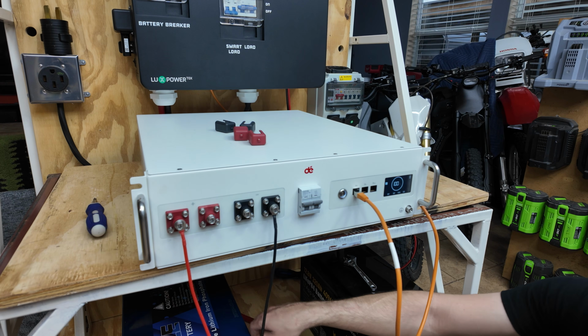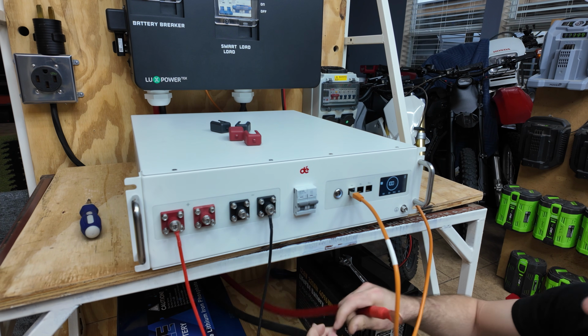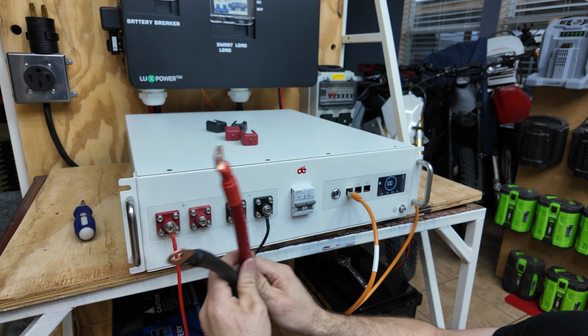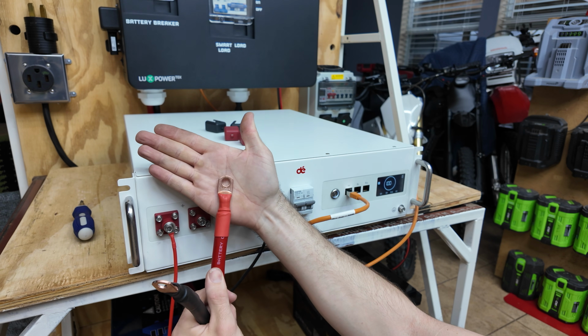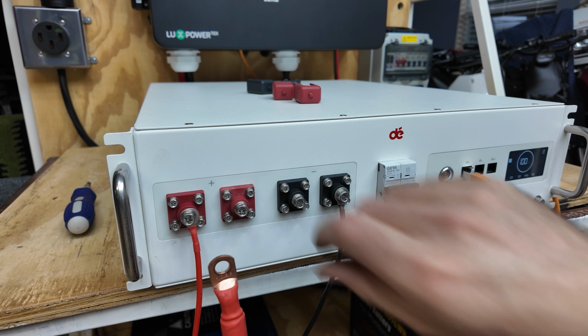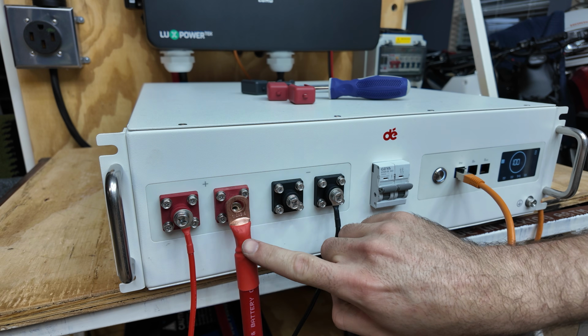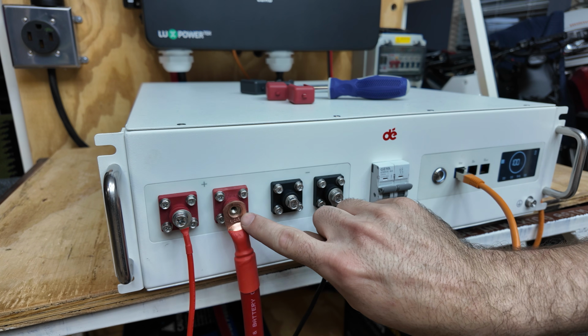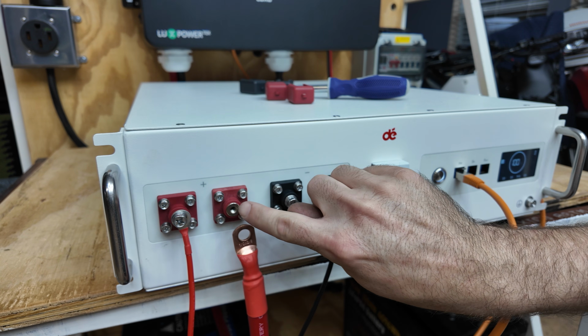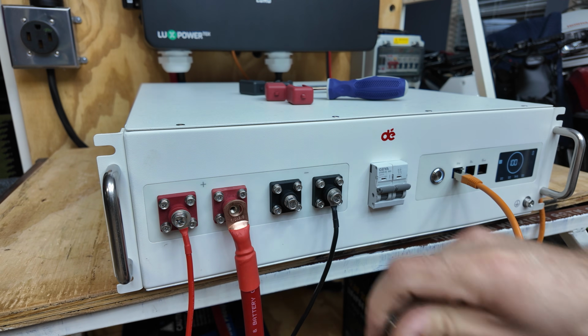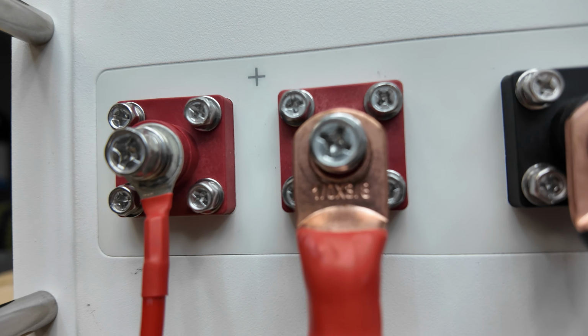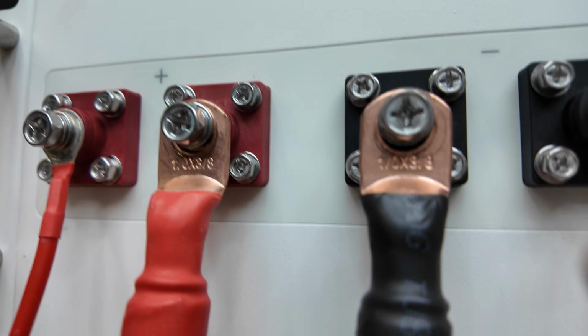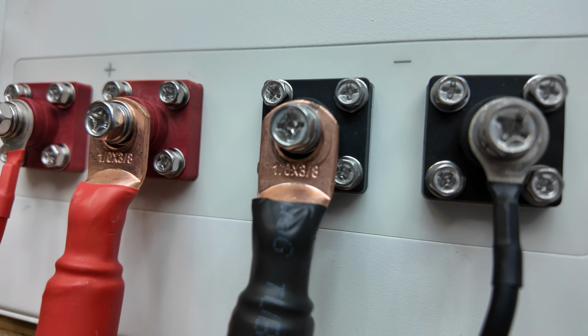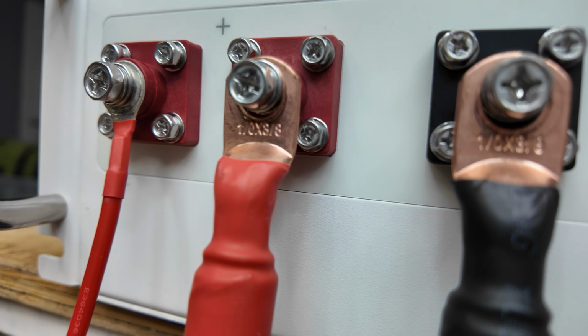Now this next part's going to be kind of tricky. I have my main inverter leads here. The problem with these leads is they're 2-aught gauge leads with massive copper lugs, so when we go to put these on, I don't think these are even going to fit. If you look where the terminal's sitting, it's almost completely on the outside of the actual terminal itself. Now it is making contact, so I am just going to connect it and run with it. So we do have a connection, and I'd say it's okay, but we have a good amount of the copper lug not even being used, just because we're not making good contact.